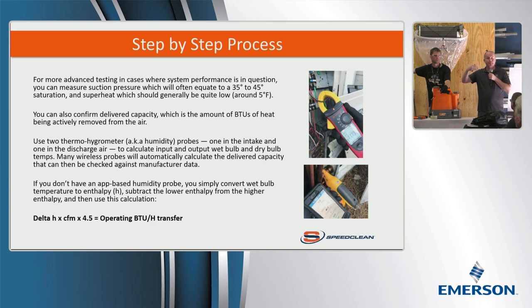You've got to look back at what the manufacturer actually produces at rated conditions to know what to expect. But if you want to give the customer that peace of mind, if as part of your procedure you want to know on a ductless maintenance that it's working, that's how you do it. I know that most people aren't going to do that. So if you're not going to do that, check suction line temperature and check your discharge air temperature. That's kind of the slacker's way.